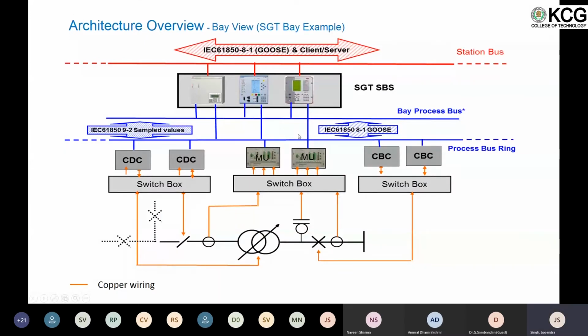This is the aim that we want to achieve. So what we have here is the transformer. This is a CT, this is a disconnector, and the circuit breakers. We connect all those devices through switch boxes. A switch box is nothing but a switching device which can have different positions available. So you can connect to one relay, you can connect to two relays, you can connect to one spare. If you want to add in future, you can add on that. This is just a switching device. It's not very common for all the utilities, but we found that this is a good thing to have. If you have this switch box, you can change it.